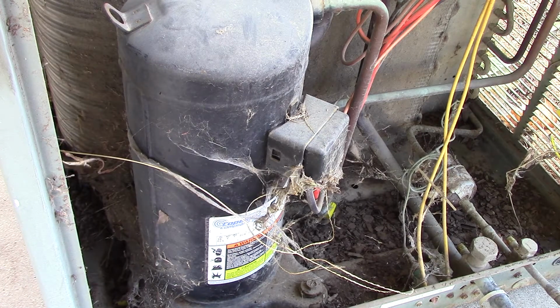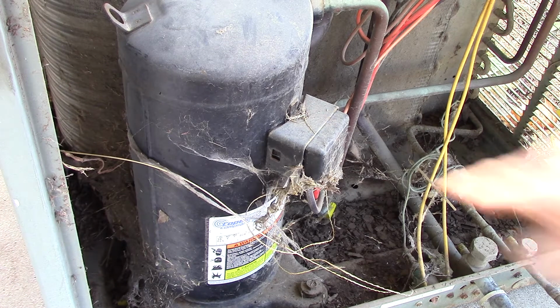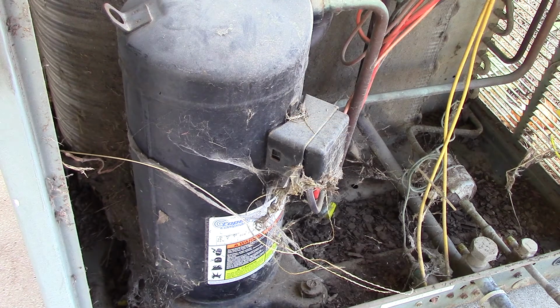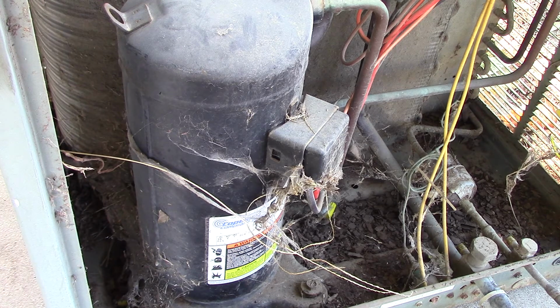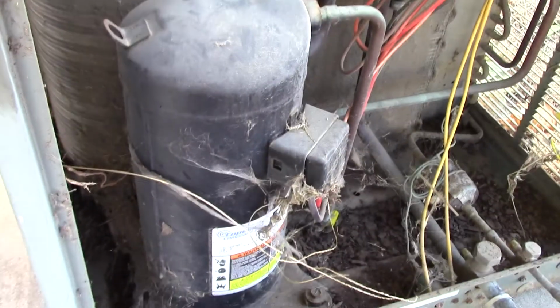So in a previous video I talked about troubleshooting on the contactor. How do you troubleshoot this bad boy right here? Well, that's your compressor. You don't want to just assume the compressor's bad and start there. Look at your symptoms. If you've tripped the double pole breaker that sends 220 volts, or 208 if it's commercial, to here, and it tries to run again and trips a breaker, this is a bad boy I'd check right here, especially if the condenser looks, well, like that.